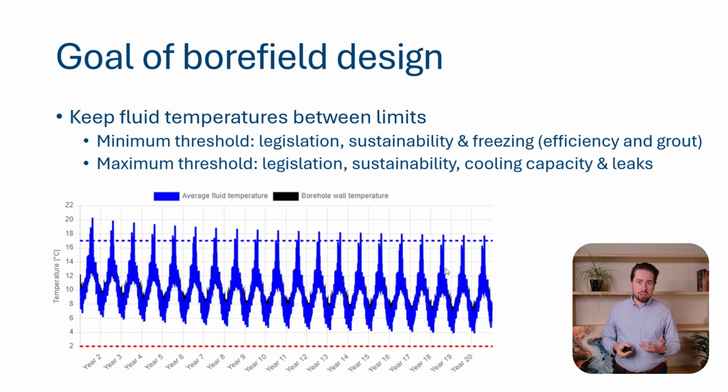The maximum temperature, you also have legislation around that in some countries. For example, you do not want more than 25 degrees going into your borefield. Also for sustainability reasons, again, it can disturb the ecosystem in the ground.